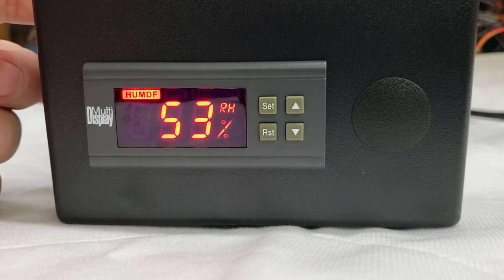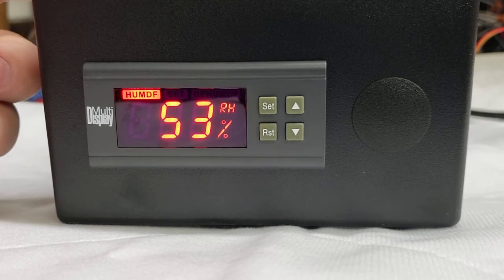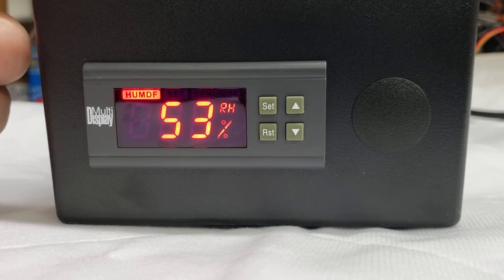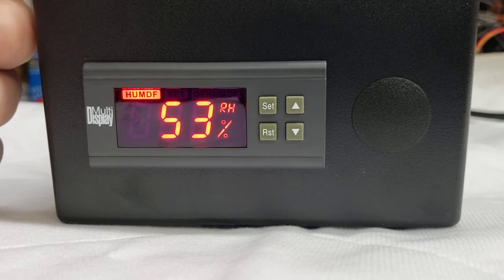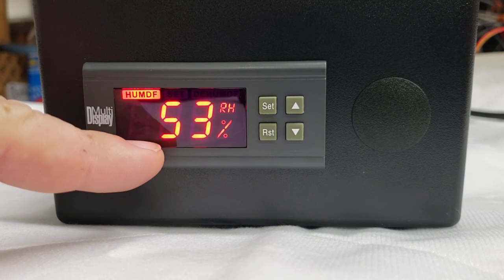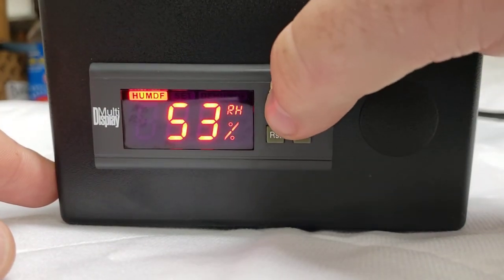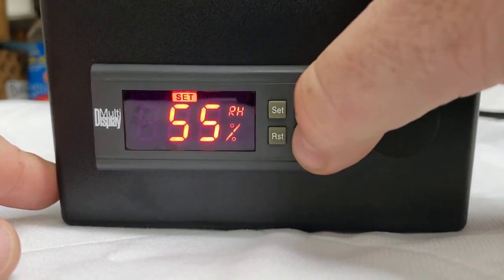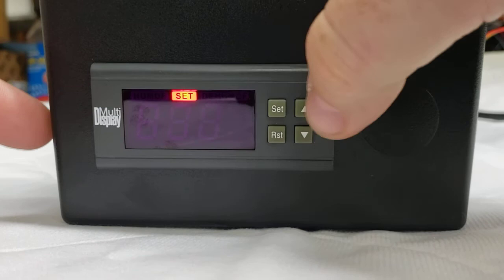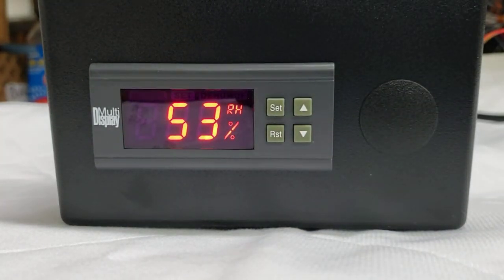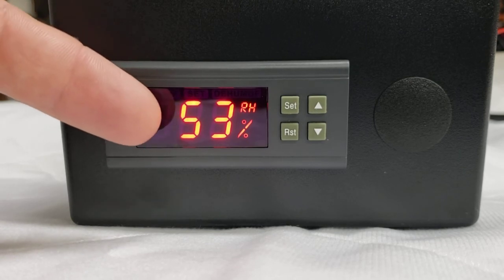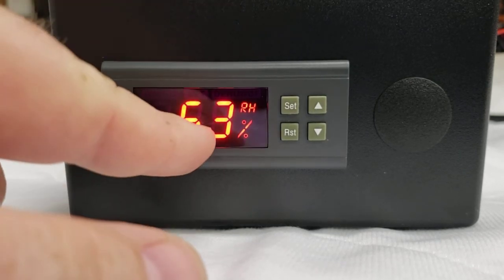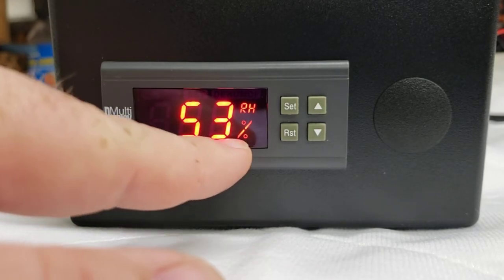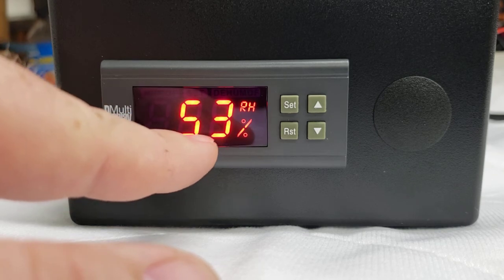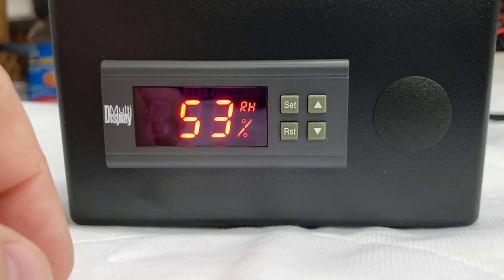What you want to do to minimize that fluctuation is use the output dial on the pump base itself, the water base. If you've ordered the digital humidity system, you want to reduce that. As that's kicking on, really dial that in so you get the minimum amount of fluctuation on the screen. Again, we're going to move this down to 50%. So we push set, down to 50, set again, and you can see now it's set for 50%. It is not going to push any humidity until this gets below 53. Basically it's telling the pump to turn off. If you've got it set for 50, when you get 1% above, it kicks the pump off. When you get 1% below, or below 49, it tells the pump to kick on. And it does that all digitally.